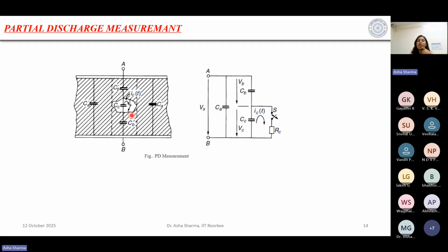So this measurement is done if there is a void or something. Some high voltage is applied across these two terminals, let's say 10 kV is applied here, but in the void, maybe some discharge occurs at a voltage lesser than that. Maybe at 5 kV the discharge is happening. So this one and this one are the two walls of the defect or the void, right? In between the two electrodes within the insulating material there is air, so some discharge is happening.